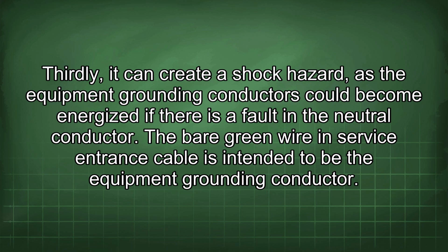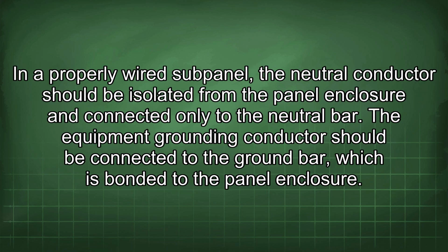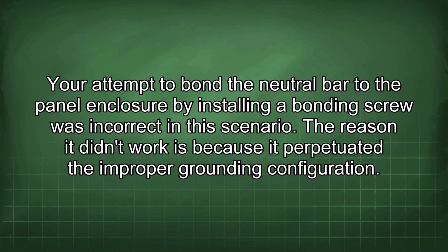in the neutral conductor. The bare green wire in service entrance cable is intended to be the equipment grounding conductor. In a properly wired subpanel, the neutral conductor should be isolated from the panel enclosure and connected only to the neutral bar. The equipment grounding conductor should be connected to the ground bar, which is bonded to the panel enclosure. Your attempt to bond the neutral bar to the panel enclosure by installing a bonding screw was incorrect in this scenario. The reason it didn't work is because it perpetuated an improper grounding configuration.